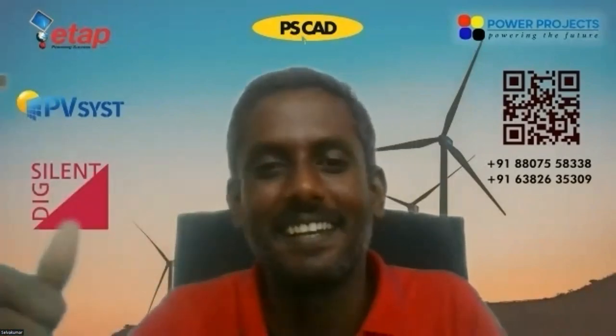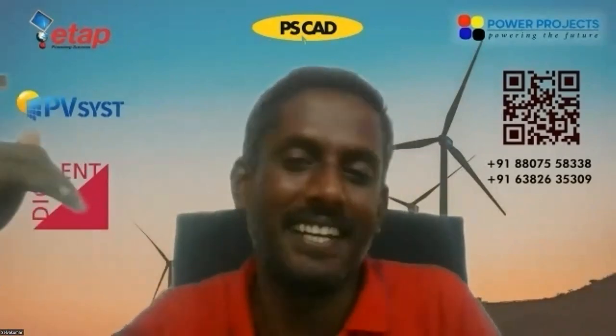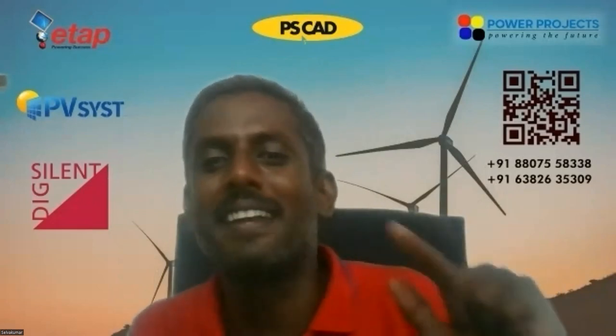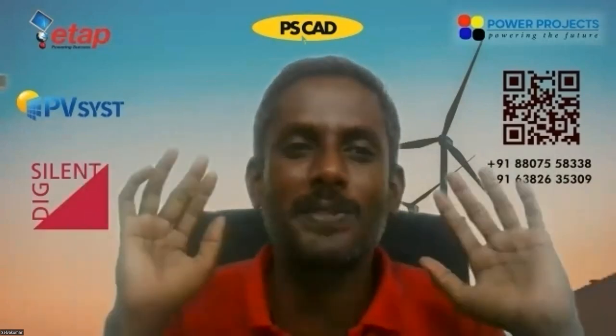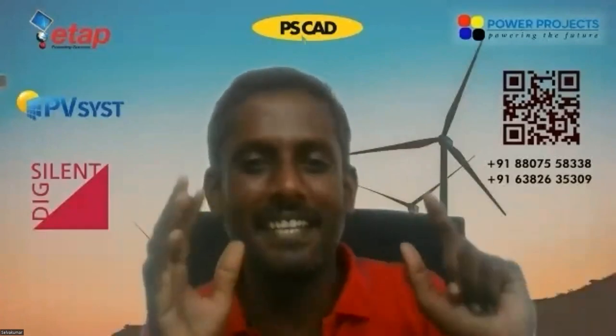That consultant comes and performs the study, and seeing that the incident energy is beyond 40 calories per centimeter square, they recommend instantaneous protection at the incomer. I'm not sure whether the company adopts that instantaneous protection at site or leaves the existing settings. But there are reported cases where, because of this arc flash study, they made the incomer setting instantaneous, just to clear the fault quickly so that the incident energy is less.